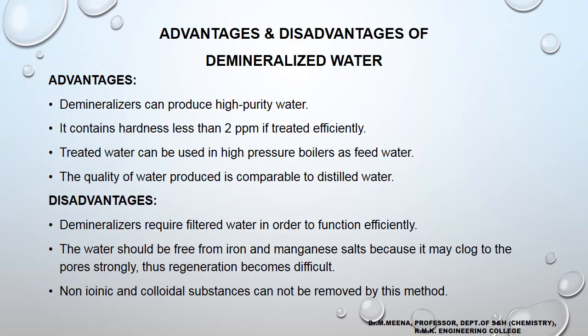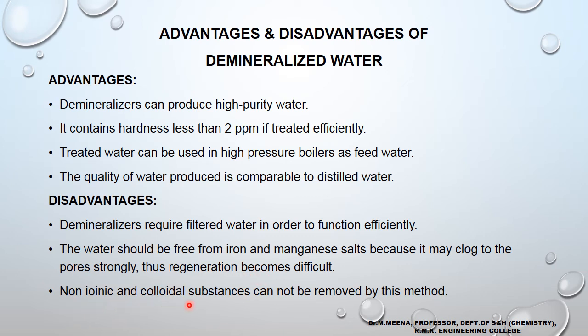Advantages: the demineralizer produces very high purity water with less than 2 ppm of hardness, making it suitable as feed water for high-pressure boilers, and the output water quality is on par with distilled water. Disadvantages: the input water must be filtered before entering the demineralizer; it must also be free from iron and manganese salts, as these block the pores of the resin making regeneration very difficult. Additionally, the demineralizer cannot treat non-ionic and colloidal impurities.